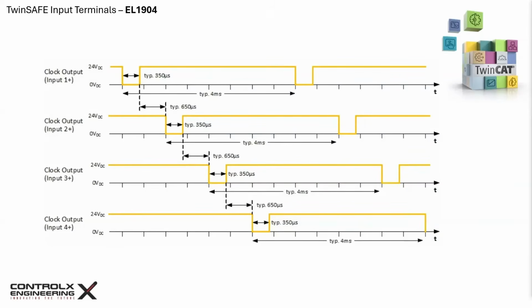I do want to point out that sometimes it might be required to disable these test pulses, for example when connecting sensors with a 24 volt output. In such cases, the 24 volt signal can be connected to the input minus connection point of the channel and disable that channel's test pulses in TwinSAFE by setting the corresponding channel's index value to false.